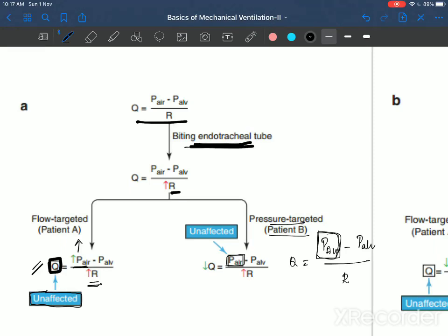The resistance has increased, so for the ventilator to deliver the pressure at your set value, your flow should decrease, because the equation's result decreases, isn't it? This is pure physics. Try not to think about this too intuitively. If the denominator increases, your final value reduces, correct?